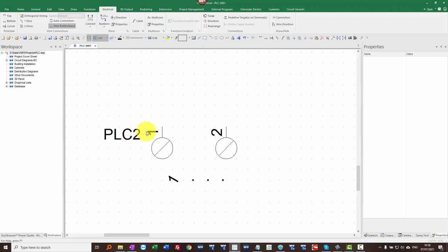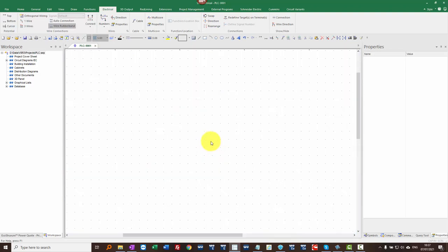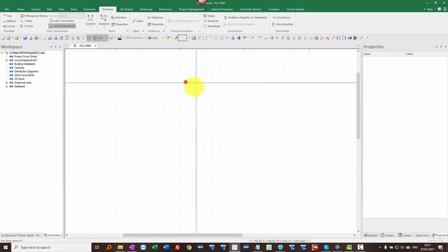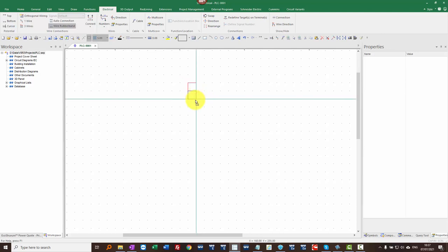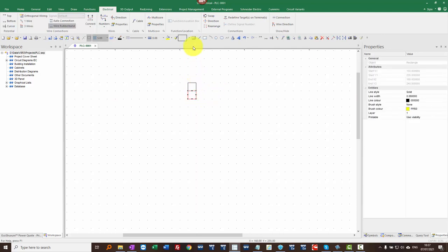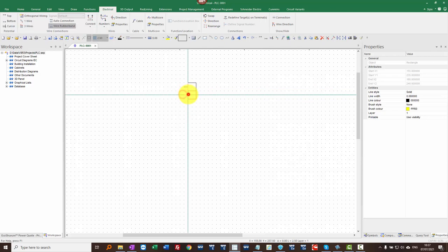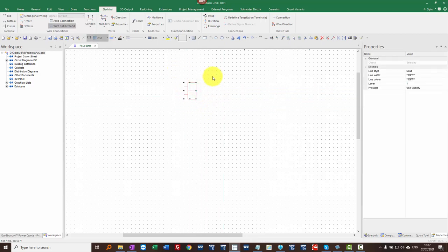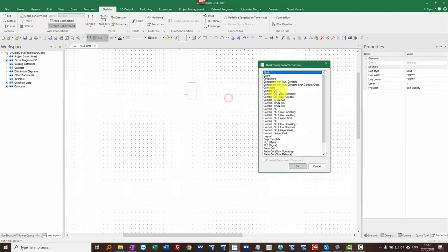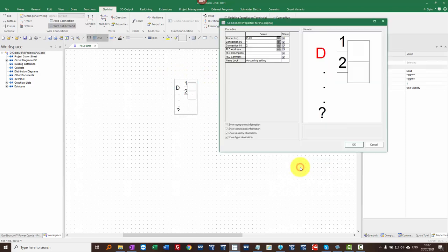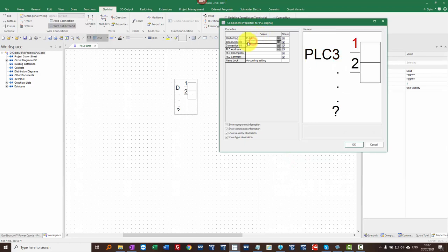So let's call it PLC2 — that's fine. Now I'm going to create the PLC main. It's made up of PLC signals, so again I'm going to do a box here, drag that down and have another one there for the other connection point. I'm going to go onto a different grid. It's important that wires are not connected to these PLC signals — they're only here for reference. I'm going to window around this, right-click and block it again as a PLC signal. I'm going to call this one PLC3, and for the connection points I'll put the address as number one.